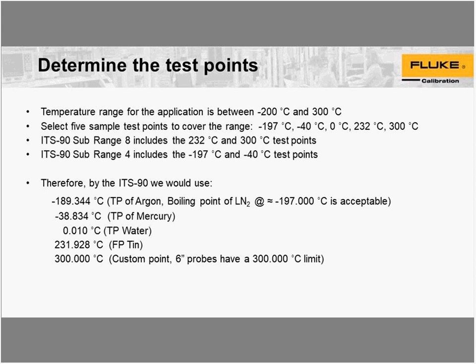All right. So if we're looking at a temperature range between minus 200 and 300 degrees, if we go by ITS-90 points, the 5 test points we would be looking at to cover would be minus 197, minus 40, or the freeze point of mercury, 0, which is the triple point of water, 232, which is the melt of tin, and 300 degrees, which is actually a non-ITS-90 point, but it's quite handy to have, so we've developed that one through time.